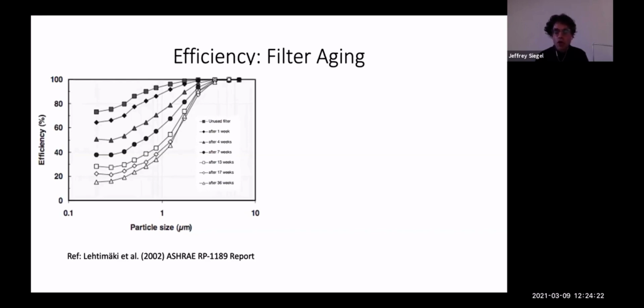And then over time, the filter efficiency declined. And it declines because part of the way the filter removes particles is it's got what's called charged media, or electret media, in the filter. And that enhances removal, but over time that effect diminishes. And so you can see that at the end, this filter was rated for a year of life, but after 9 months, that's the white triangles at the bottom, you can see it's declined in performance quite substantially, particularly for smaller particles.